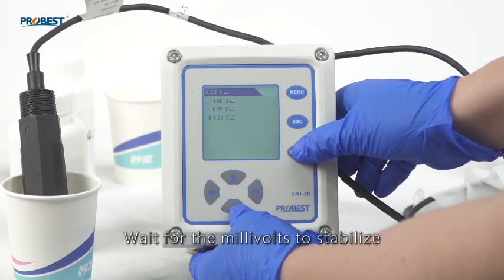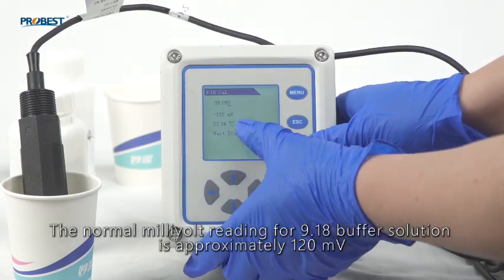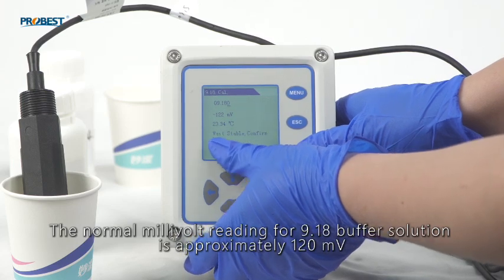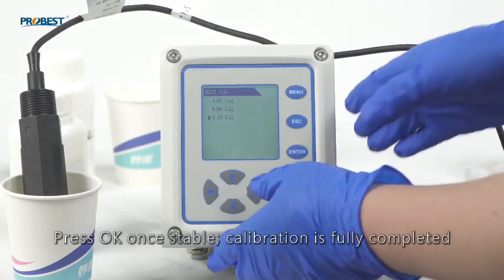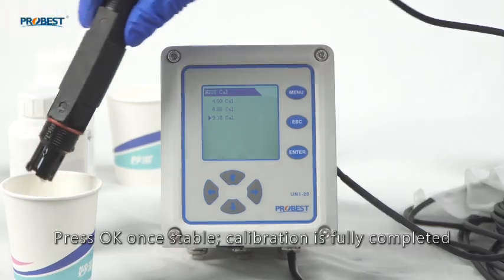Wait for the millivolts to stabilize. The normal millivolt reading for 9.18 buffer solution is approximately 120 mV. Press OK once stable. Calibration is fully completed.